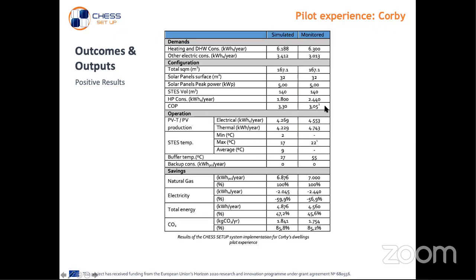The COP on the heat pump was slightly less than we hoped for. In fact, our target simulation was still less than we'd aimed for. We had a target in mind of 4 on the COP, and we're still working on why we think we've fallen short. There are a number of theories we're still working through with the data towards the end of the project to resolve that.